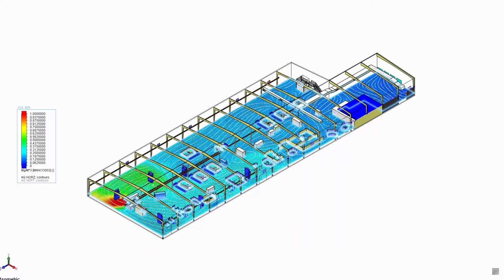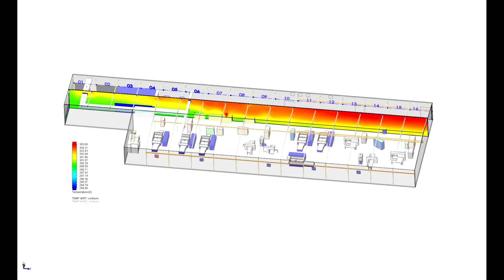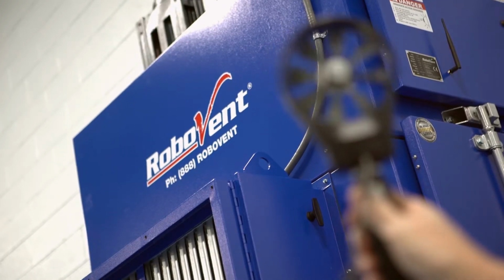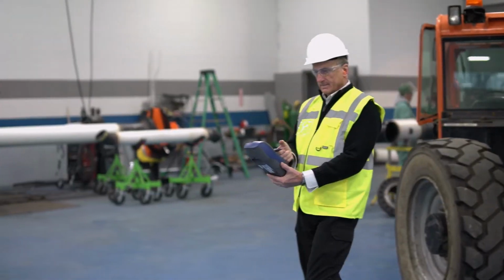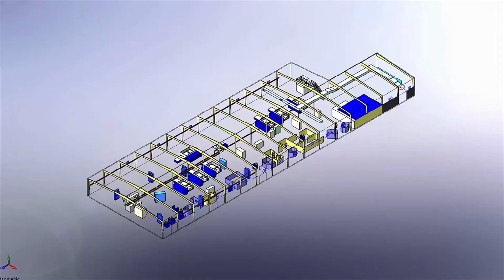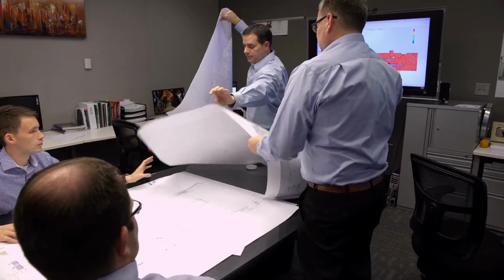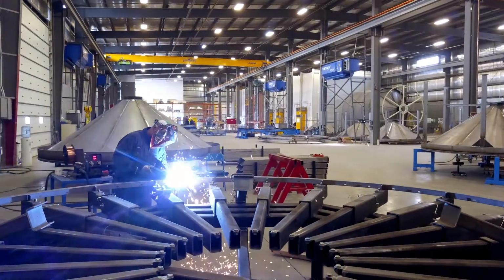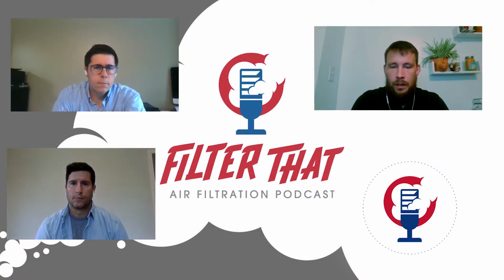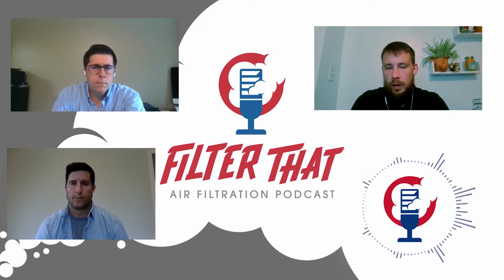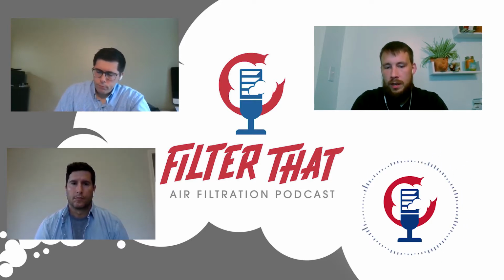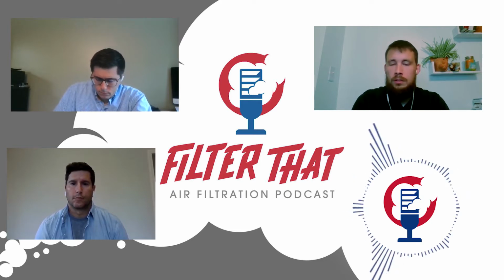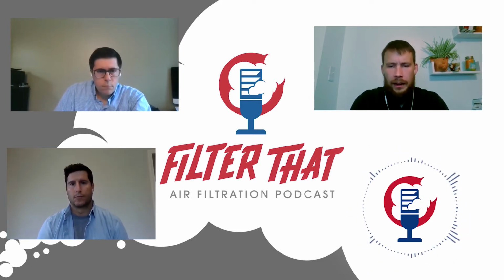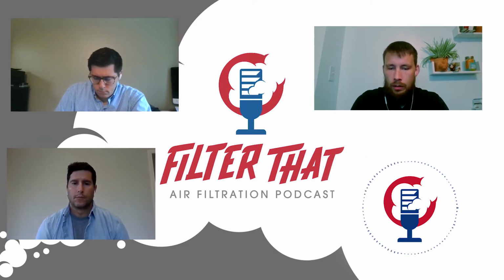Weld fume is one that we've developed with other companies that help us create what we call cut plots. We show graphs essentially of where the particulate is going to be concentrating in a facility, in a hood, in a backdraft, anything we decide to do the simulation on. We can do heat load studies using this too, assigning a heat generation rate from a press or an oven to show what the temperature inside the building is going to do if you shut off one of those processes, add air conditioning, or just change general airflow.